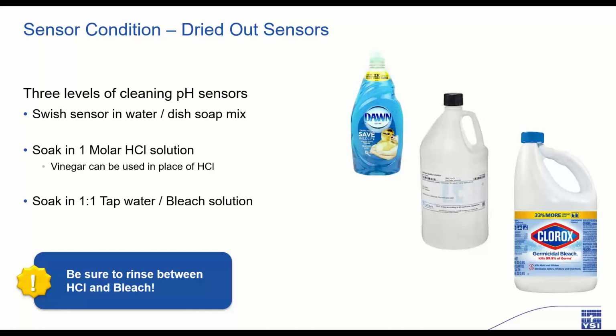The next step, for more severe foggy type coating on the glass, you might try a short 20-minute soak in 1 molar HCl solution. This will help clean any tough contamination off of the glass bulb. The third and final cleaning attempt, and honestly my go-to cleaning procedure, would be another short 20-minute soak in 1:1 tap water to bleach solution. This will help break down any biofouling that might be clogging the reference junction and slowing down the response time of the pH sensor.